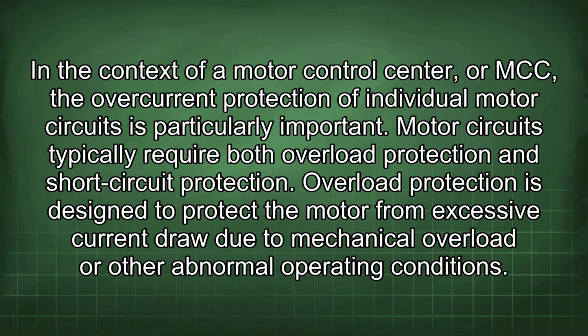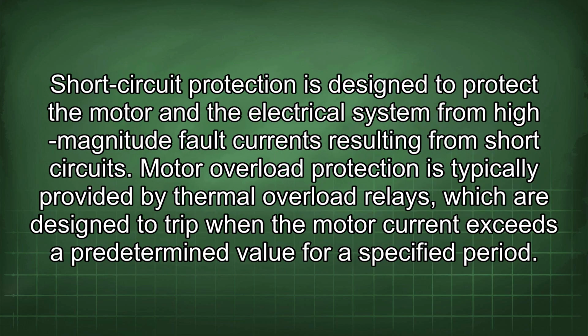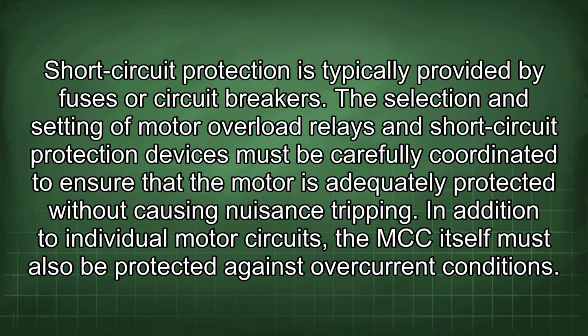In the context of a motor control center, or MCC, the overcurrent protection of individual motor circuits is particularly important. Motor circuits typically require both overload protection and short circuit protection. Overload protection is designed to protect the motor from excessive current draw due to mechanical overload or other abnormal operating conditions. Short circuit protection is designed to protect the motor and the electrical system from high magnitude fault currents resulting from short circuits. Motor overload protection is typically provided by thermal overload relays, which are designed to trip when the motor current exceeds a predetermined value for a specified period. Short circuit protection is typically provided by fuses or circuit breakers. The selection and setting of motor overload relays and short circuit protection devices must be carefully coordinated to ensure that the motor is adequately protected without causing nuisance tripping.